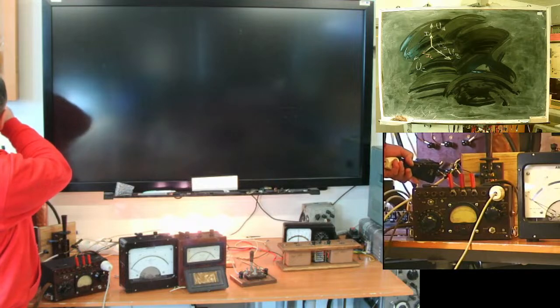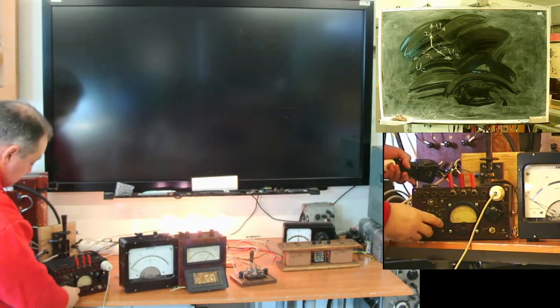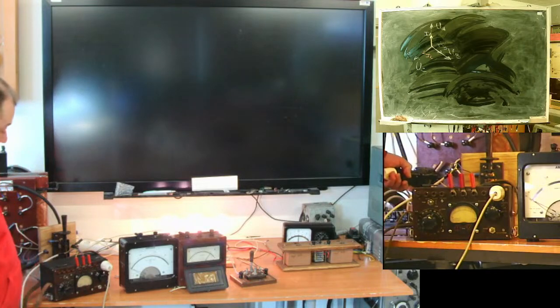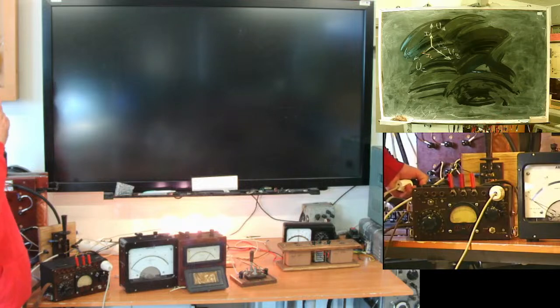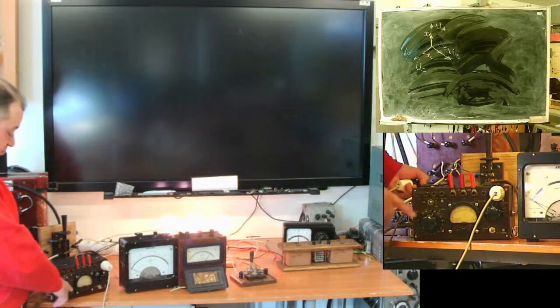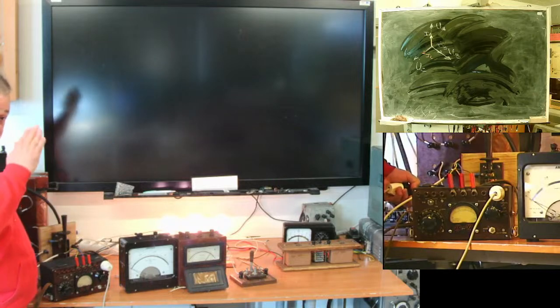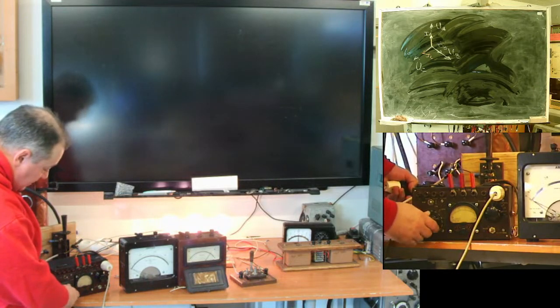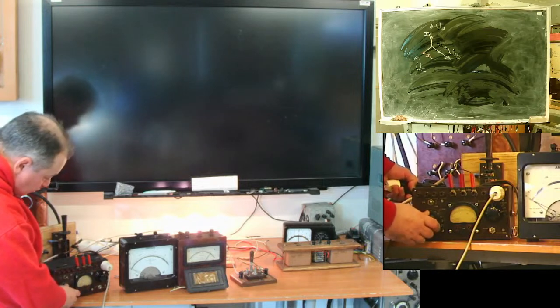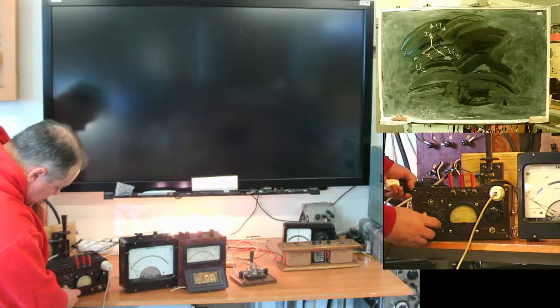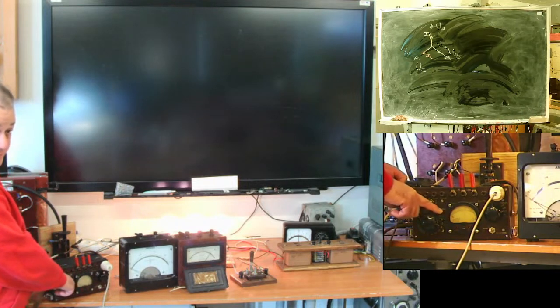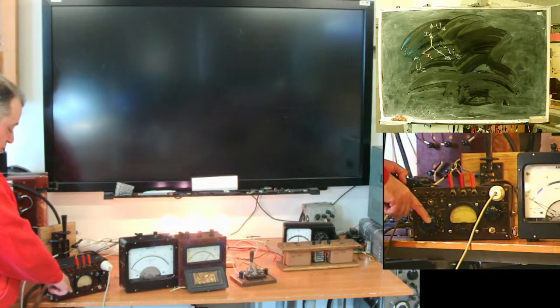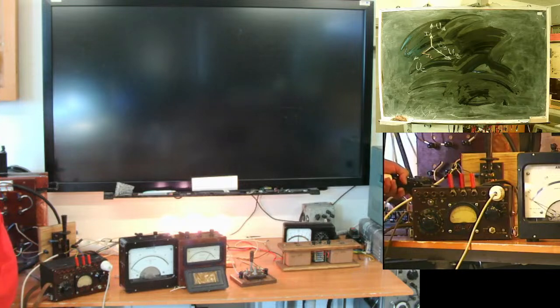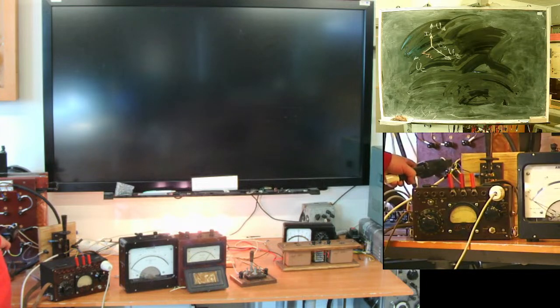It's powered from three-phase network, and with this knob, inside is a device similar to my demo model of rotating field. This thing produces voltage with controlled angle, and this voltage is compared to voltage proportional to current. So if I set to 0, see, now it's showing 0. At the moment it shows 0, the angle of this controlled voltage is equal to the angle of current vector onto A phase.